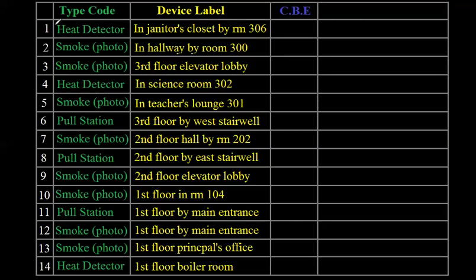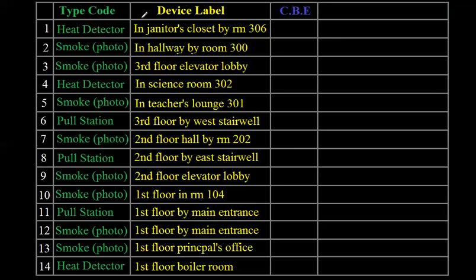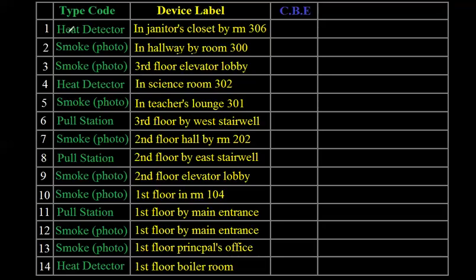It cares about the heat detector. And then we'll give it a label. And that's more for the human interaction with the panel. If it were a fireman that were coming in to figure out where the alarm was, that's for them. Or if it was somebody trying to troubleshoot a problem, that's for us. The panel doesn't care that device one is in a janitor's closet by room 306. It's not going to check the janitor's closet in room 306. It's going to check for device one. So I could label this whatever I want and it's only to help guide a user to that device. For each device I went through, smoke detector and I gave it a label. Device three, smoke detector, gave it another label and so on and so on.